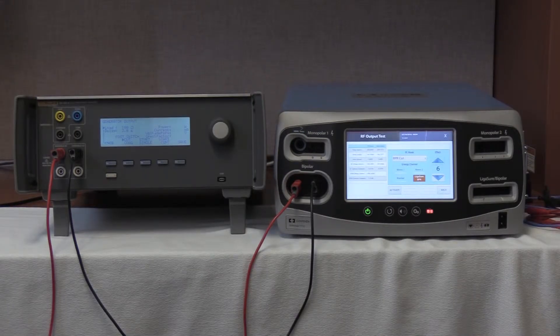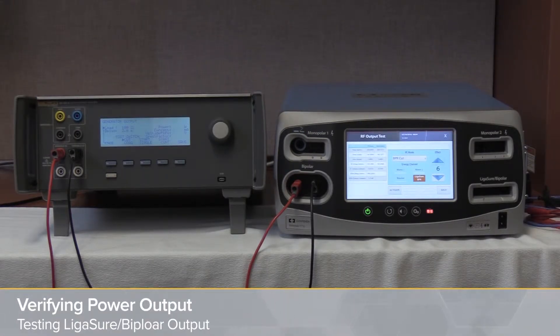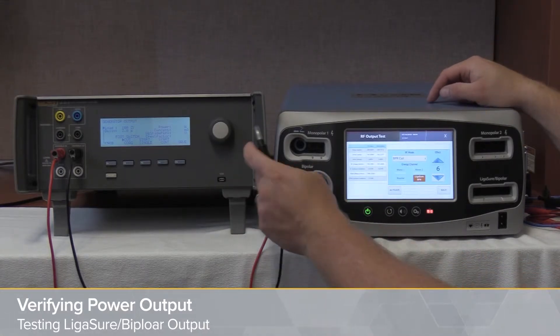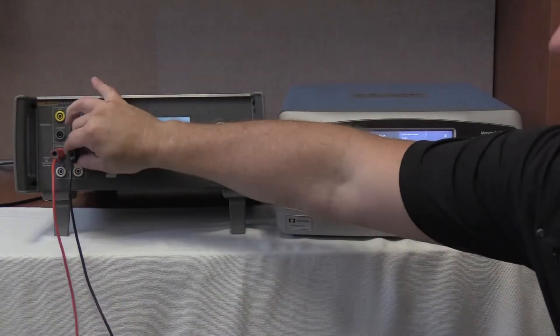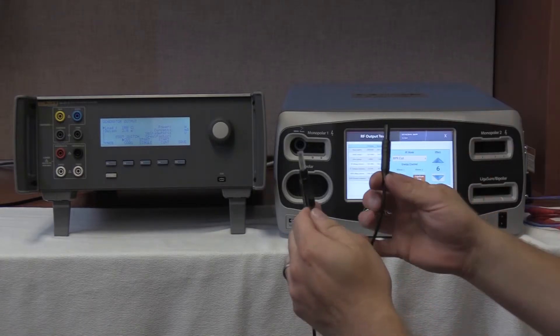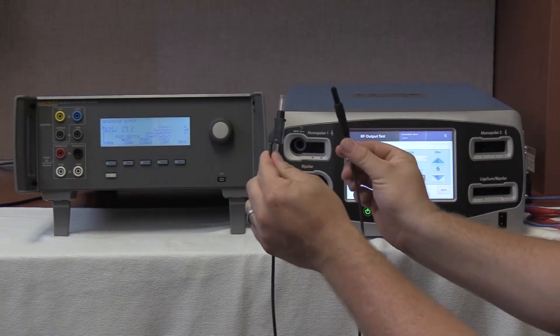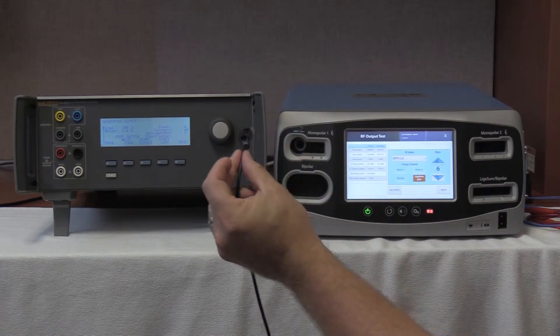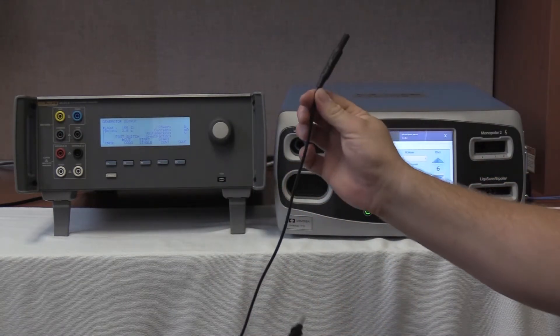Final section of testing covers the LigaSure and bipolar output of the Valleylab Covidien FT10. We are going to disconnect the bipolar cables used in the previous step and replace them with the bipolar LigaSure cables found in the QES3. When looking at the LigaSure cables, you can see a distinct difference: this is the bipolar cable, this is the normal output cable, and this is the bipolar LigaSure cable.